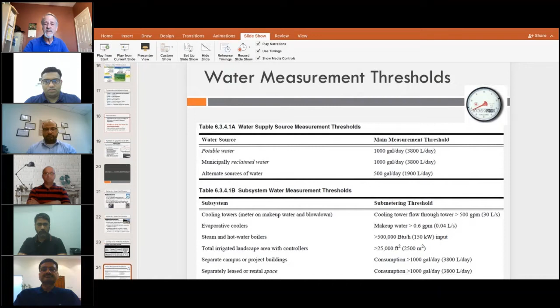And just picking one quick example right here, for a cooling tower, if you have the total flow through the cooling tower of greater than 30 liters per second, which is not that big, at least you have a makeup signal on there. You're recording how much makeup water is being used. And then, so now you know at that point. And then perhaps if something goes wrong, a valve fails, and you start using more water, well, that recording signal could detect that and at least send you a note that, hey, something happened here.